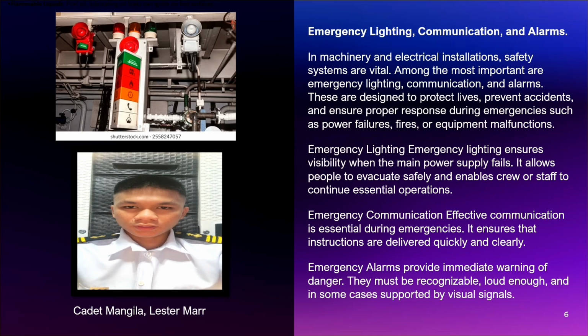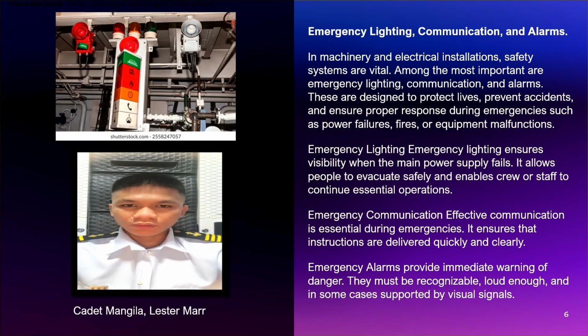First is escape route lighting. These are lights installed along hallways, stairways, and exit doors, guiding people to safety. Next is open area or anti-panic lighting. Used in large spaces like machinery rooms or halls para hindi magpanik ang tao at makita pa rin nila ang paligid. And last is high-risk task lighting. Placed in areas where people operate dangerous equipment so they can still shut down machinery safely during a blackout.